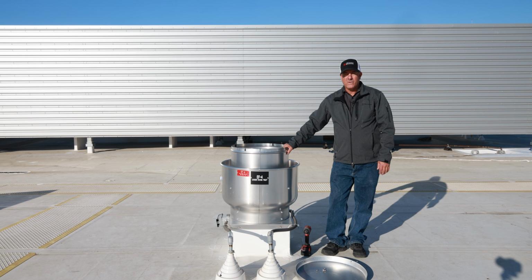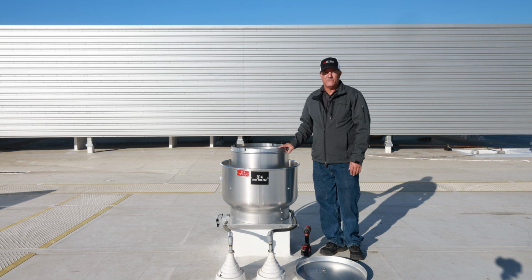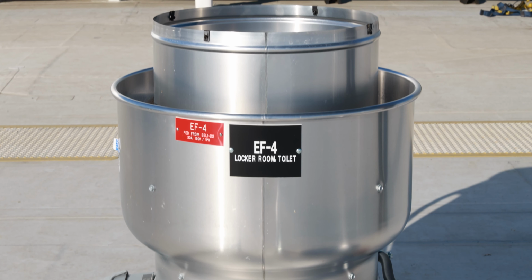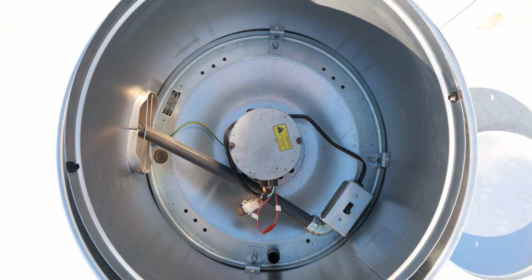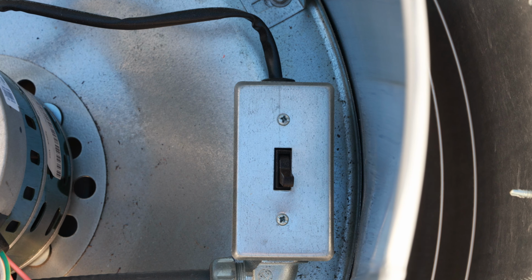Okay, exhaust fan 4 on the roof. This is similar to 5 other fans on the roof. They're direct drive fans, no belts to maintain. They do have a disconnect inside the fan.